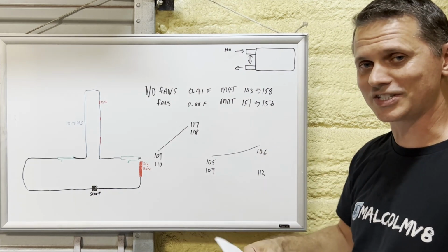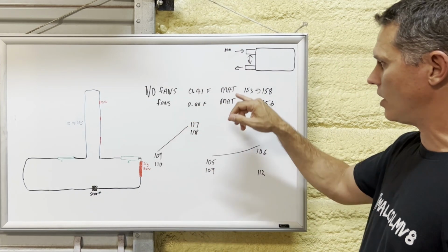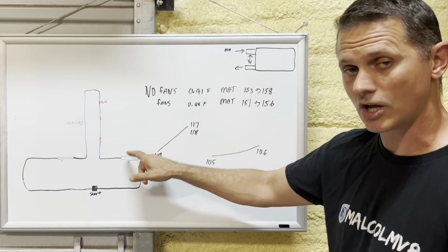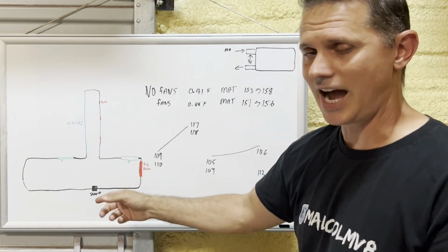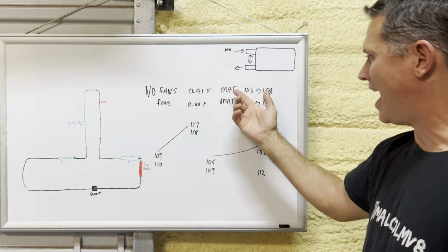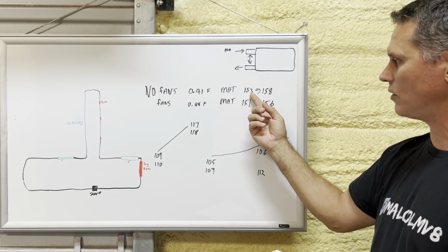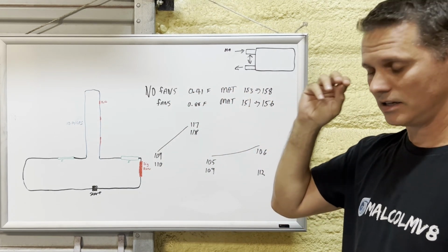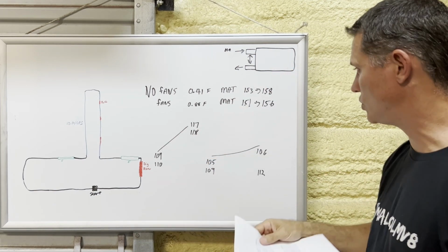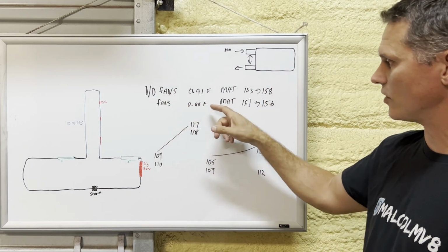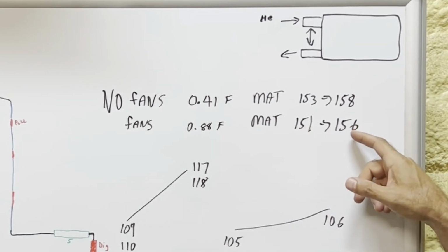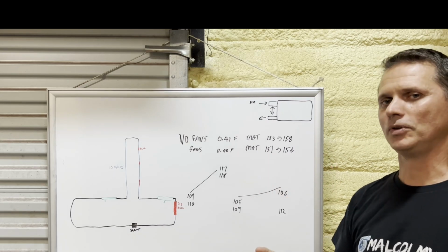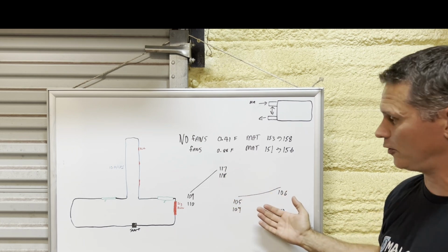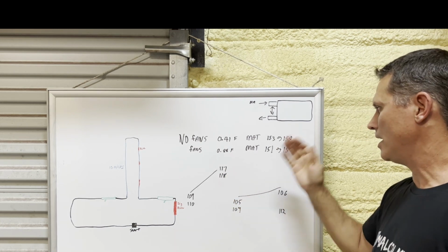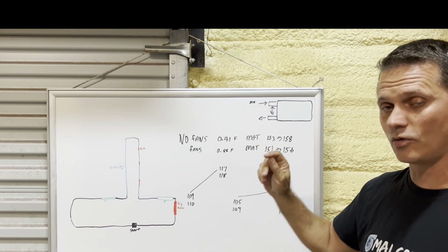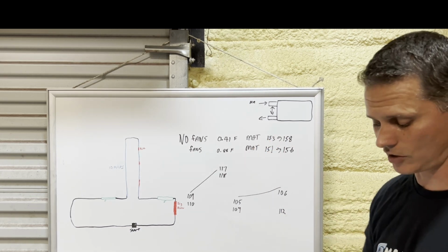I'm actually surprised we were able to see the difference, but averaging over all of our logs, talking about the second block specifically, after doing the heavy highway runs and the hard pulls, our average temperatures would be between 153 to 158 IAT2, air intake temp 2, after the blower. When we had the fans on the system, it would be about 151 to 156. So we're talking a couple degrees improvement, a few more degrees on the fluid, but the temp is about there. Although idle is not the greatest way to read it, the results are fairly consistent across all of the tests.